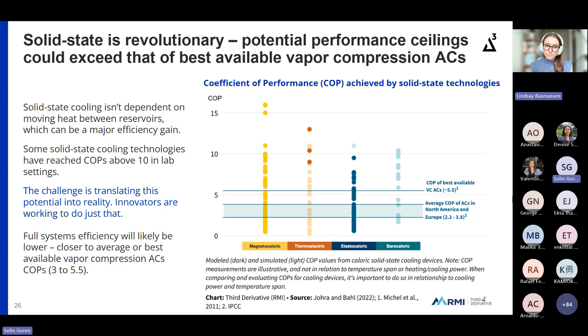Solid-state researchers have shown COPs above 10 and even 15 in lab settings for solid-state components specifically, which is incredibly exciting and speaks to the potential of this technology class. However, it's important to note those components are just one piece of larger cooling systems, so as you integrate that component into the larger system, you tend to lose some of those efficiency gains. This means we'll likely see solid state cooling technologies closer to or above at-market vapor compression technology, or even closer to that best-in-class threshold. This is exactly what innovators are focusing on right now: translating that potential into reality.